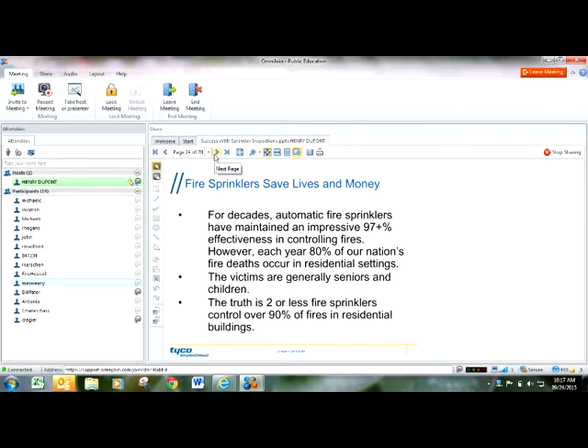Another myth of sprinkler systems is that your standard sprinkler system is designed to extinguish fires. Standard sprinkler systems are designed to control fires until the AHJ, the firefighters, arrive. But most times the sprinklers do put the fire out before the fire department arrives.